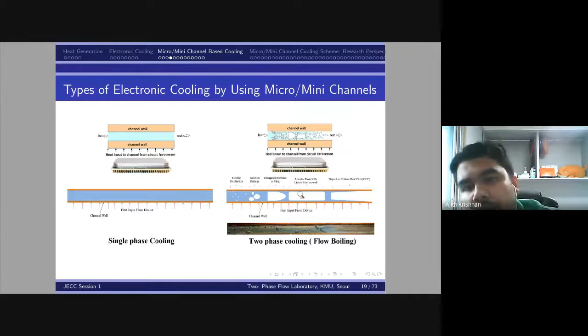You can see here there is an old 1 rupee coin, and small test channels that have been built on a small block. You can approximate the channel size here, how small it was. This was around 0.4 mm opening, this one 0.5 mm opening, and this one 0.6 mm opening. You can see 0.2 to 0.6 - this is the range of channel size that we have adopted in order to cool electronic devices.